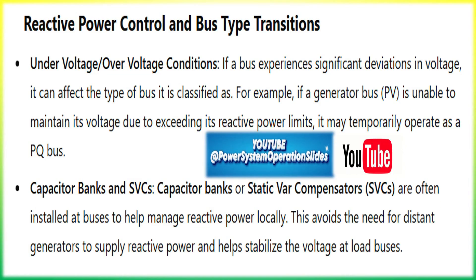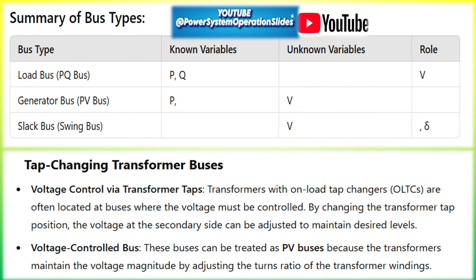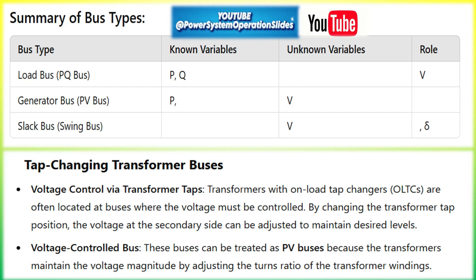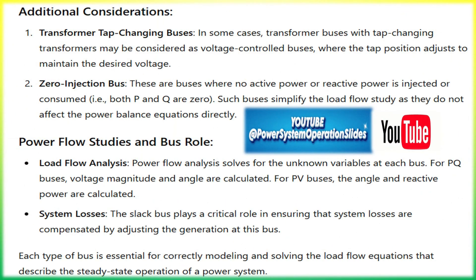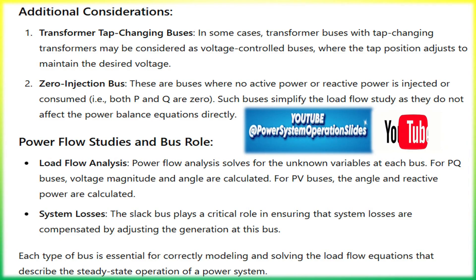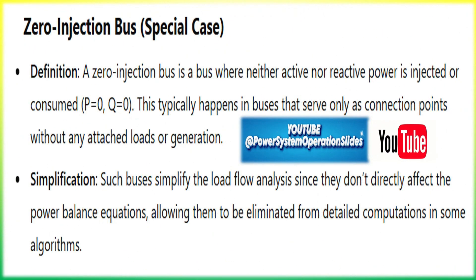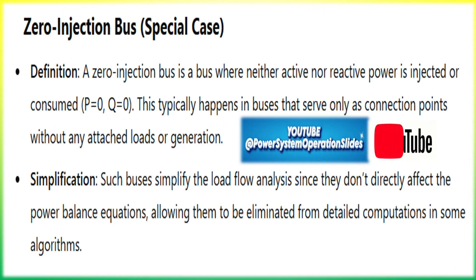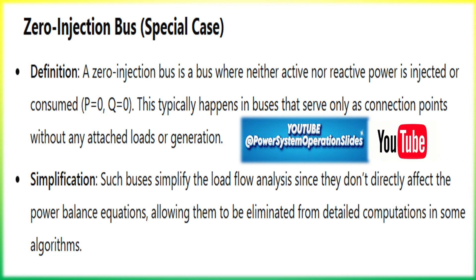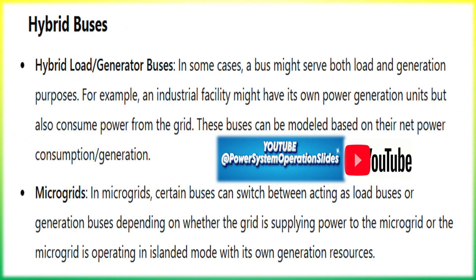Voltage regulation: at generator buses, the voltage magnitude is kept constant by adjusting the reactive power output of the generator. This helps maintain voltage levels across the grid, which is essential for stability and reliability of power delivery. AVR — automatic voltage regulator: most generators are equipped with an AVR that senses voltage levels and adjusts the generator's excitation to maintain a set voltage level. This is why voltage magnitude V is specified for PV buses, as the generator compensates for reactive power variations automatically. There are physical limits on reactive power; beyond these limits the bus could be converted from a PV bus to a PQ bus, which occurs if the generator cannot maintain the required voltage while staying within its reactive power limits.